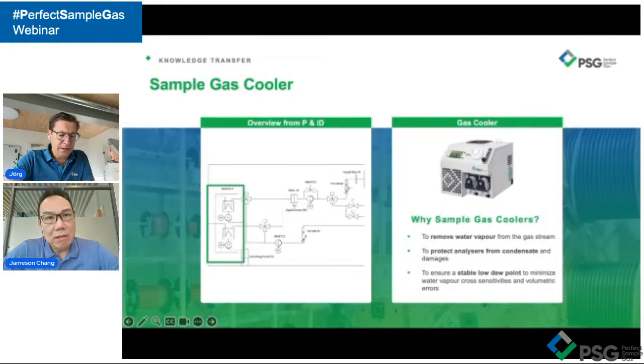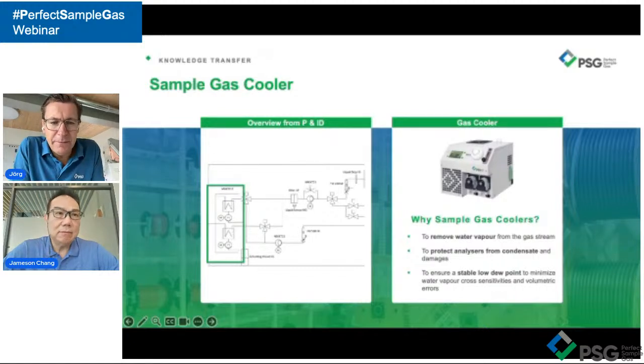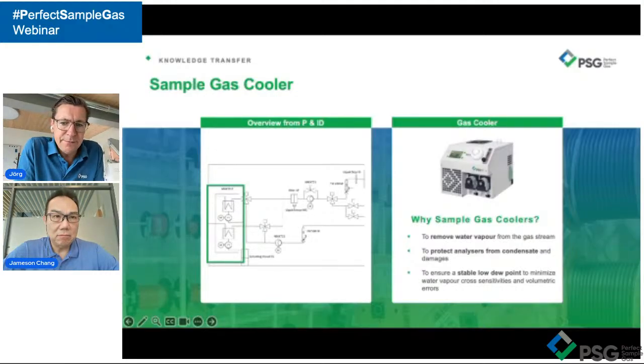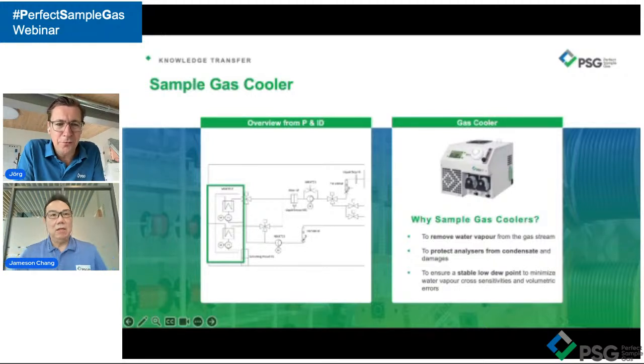But as you said, cold dry systems are still a very big part of the analyzer systems. As you said, these multi-gas component systems like FTIR, the hot wet solutions, there are some applications where they are almost over the top. If you just have to measure, let's say, the three main components, CO, SO2, NO, then you would prefer maybe to go for a cold dry system, right?